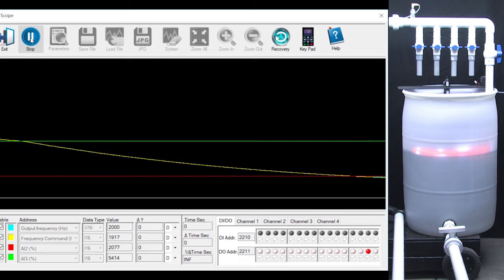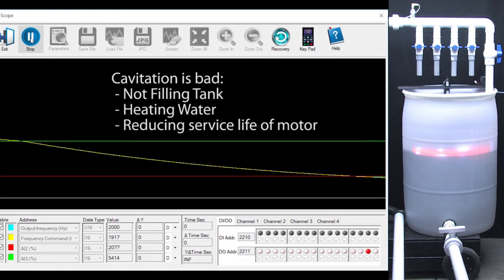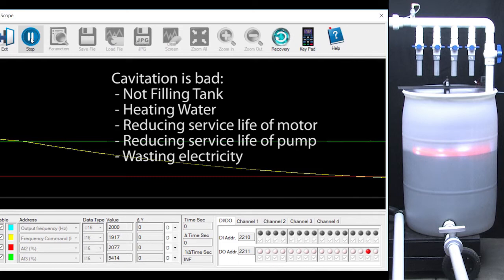The second issue is, again, since the motor is going slower and slower as the tank fills, eventually the motor speed will get to the point where the centrifugal pump is spinning too slow to move the water and it will sit there and cavitate, which means it's not filling the tank, it's heating up the water, it's reducing the service life of the motor, it's reducing the service life of the pump, it's wasting your electricity and it's wasting your money.